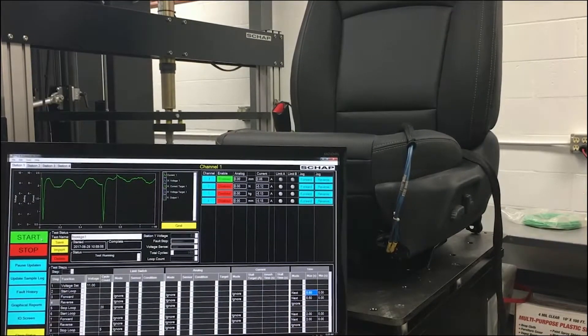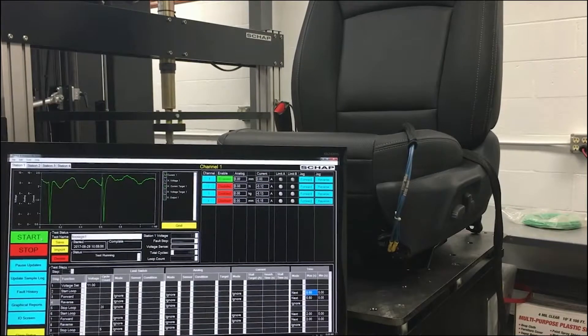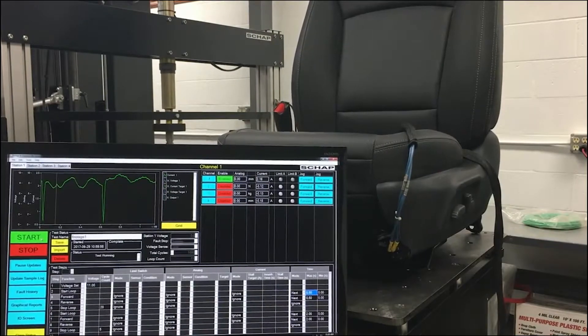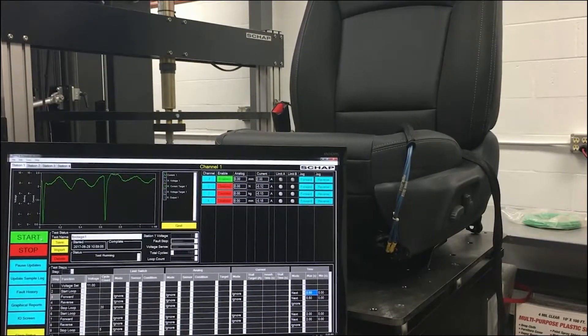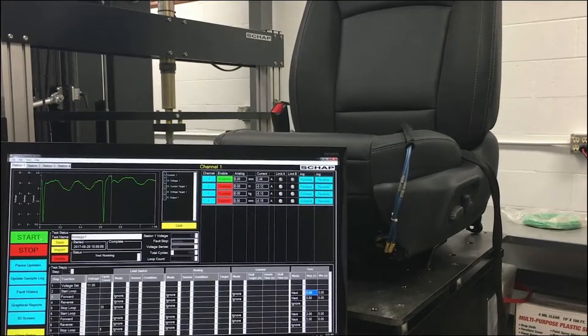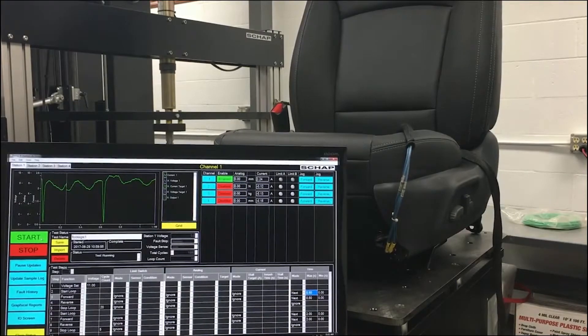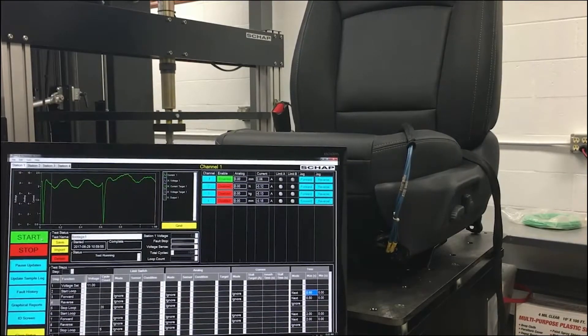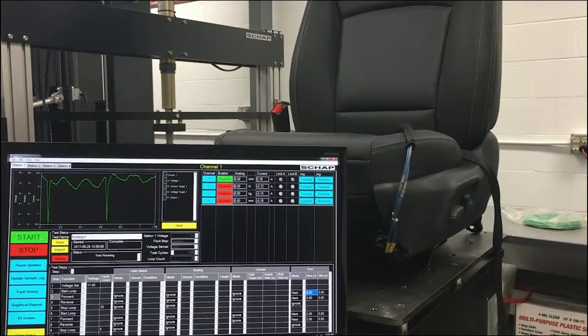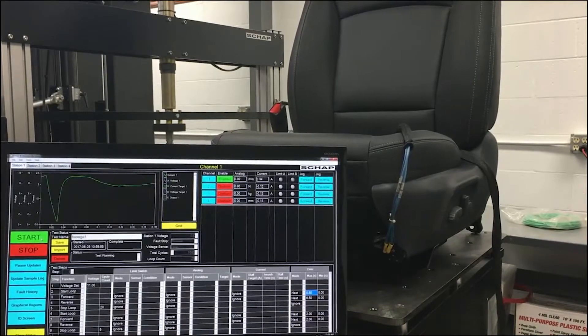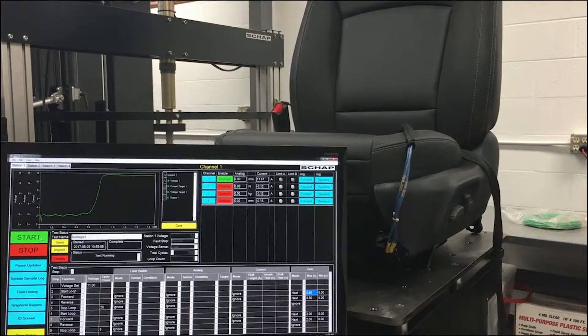The last condition is time. A common idiom in programming the tester is to enter a step with the wait function, a time mode of next, and a maximum of zero seconds. This causes the channel to be ignored entirely for this step.